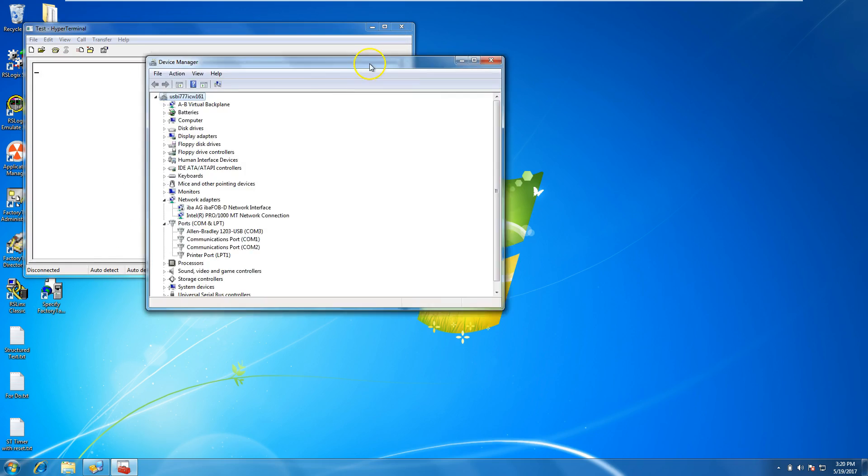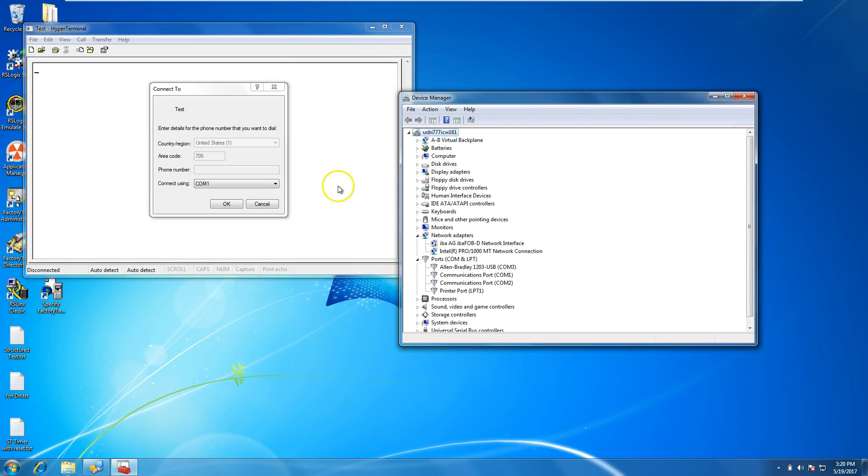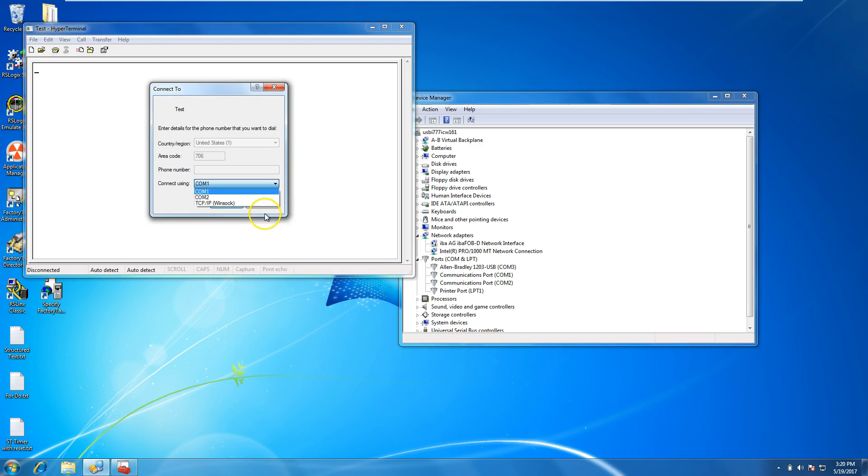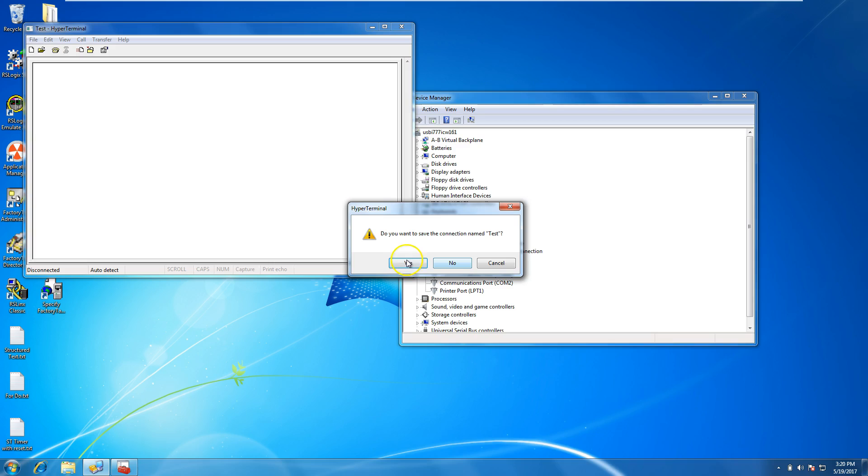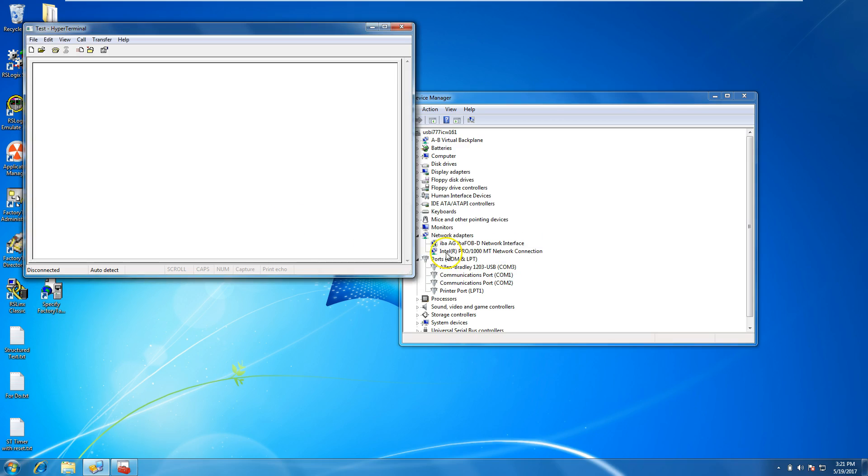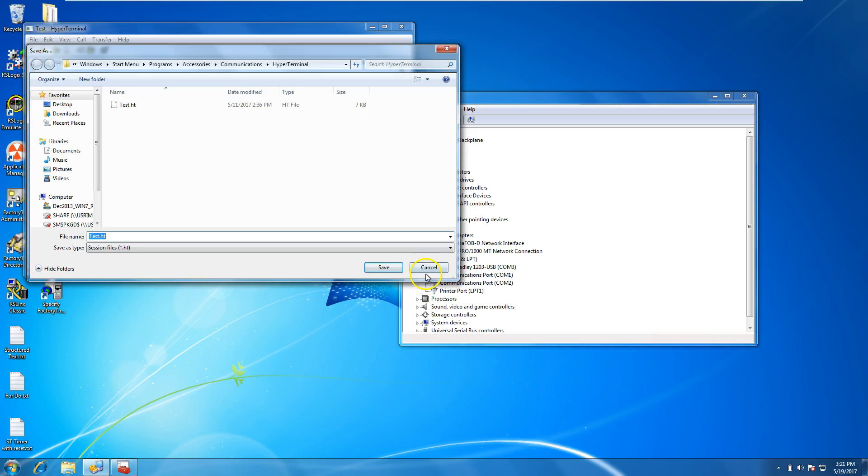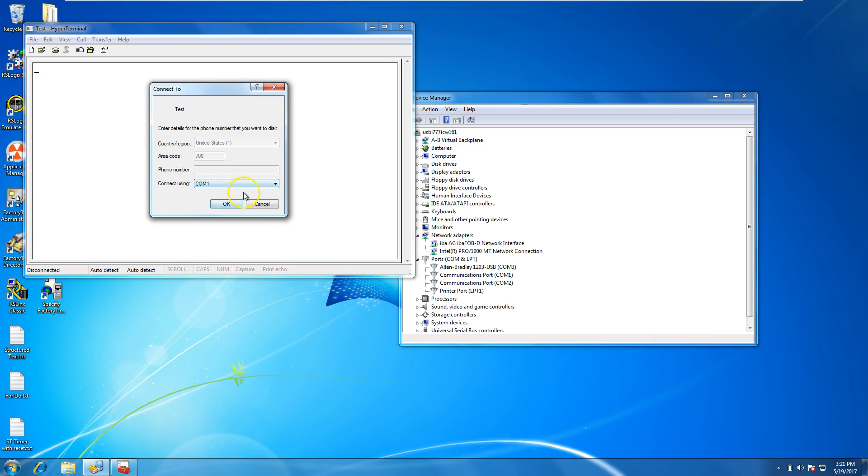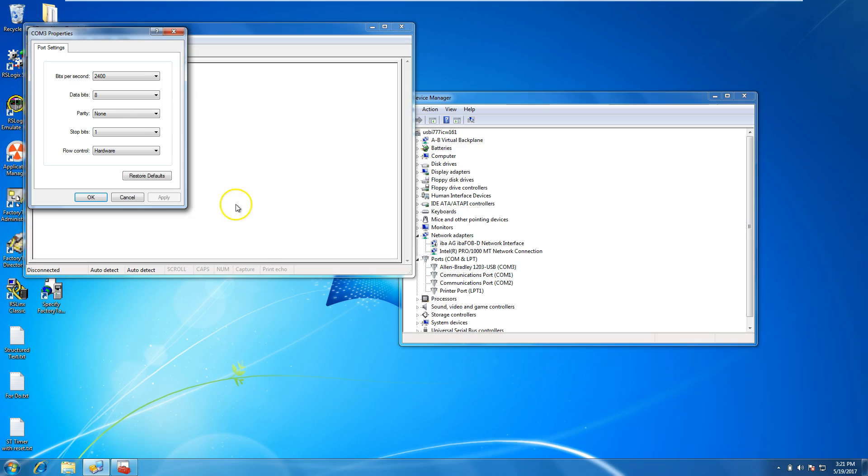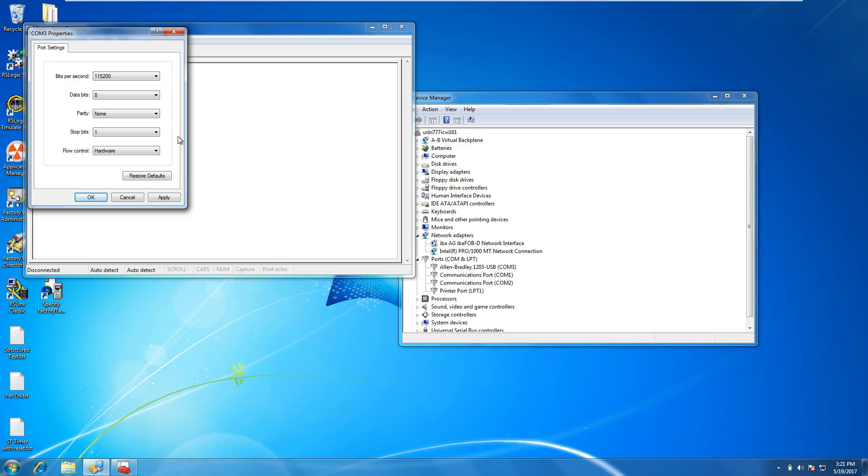We'll do a new connection, call it Test, and select COM 3. When you select COM 3, you want to change to 115200, which is the standard for communicating to a drive from a 1203 USB, which is a USB to serial connection. Leave the rest of this fine.